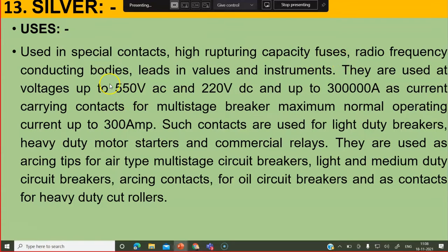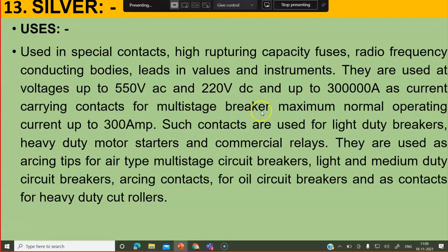Silver is used in radio frequency conducting bodies, leads in valves and instruments. They are used at voltages of 550 volt AC and 220 volt DC. Because in DC and AC, heat produced is different, so ratings for AC and DC are very different. Up to 300 ampere as current carrying contacts for multi-stage breakers. Generally circuit breaker contacts — maximum normal operating current 300 ampere — are used for light duty breakers, heavy duty motor starters and commercial relays.